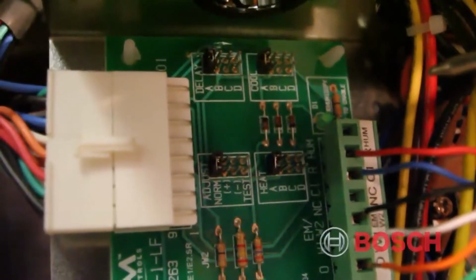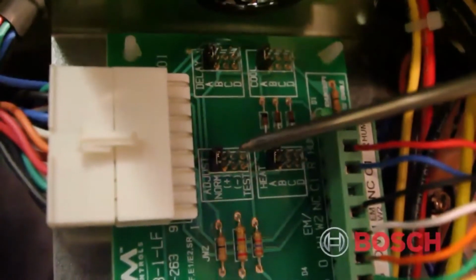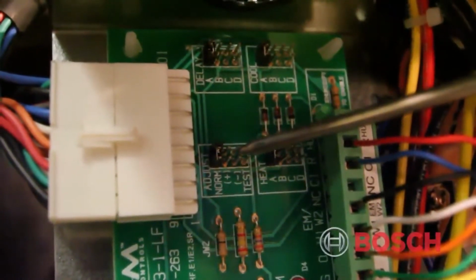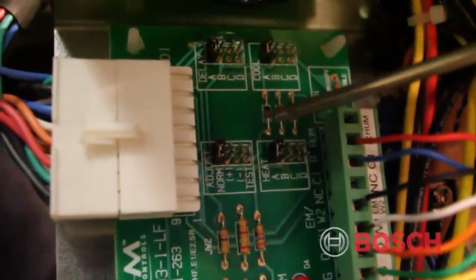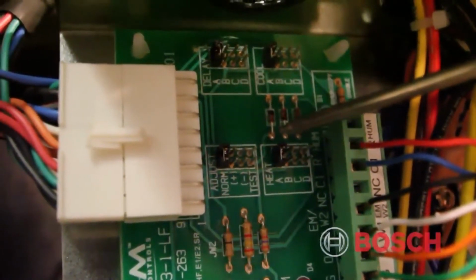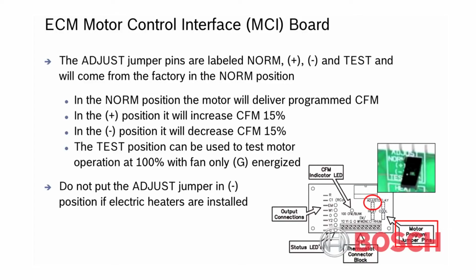The adjustment jumper is going to come from the factory in the normal position. This will give you your normal selected nominal CFM. There is also a plus and a minus position. The plus position allows you to increase CFM by 15%, and the minus position allows you to decrease CFM by 15%, depending on where the heating, cooling, and delay jumpers are located.